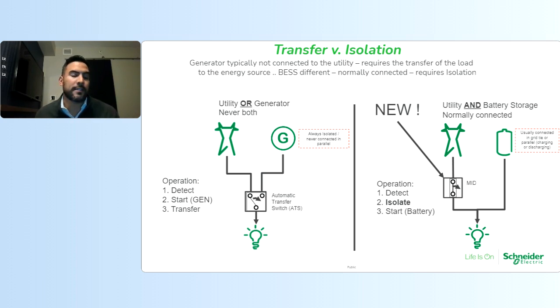And the reason for that is, the transfer switch requires a power source to energize our solenoid operator, the transfer switch operator, to transfer load from source one to source two. If there's no source two present, the transfer switch will stay connected to source one, which distinguishes the key differentiated piece here, where an automatic interconnection switch also comes with the controller.